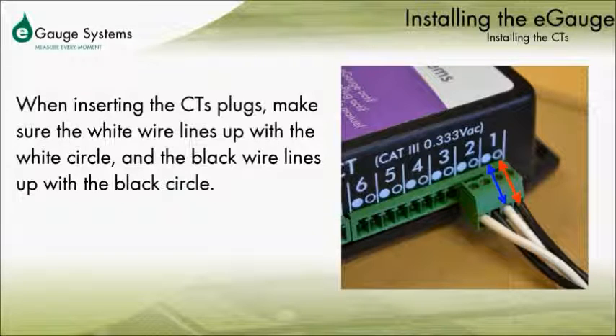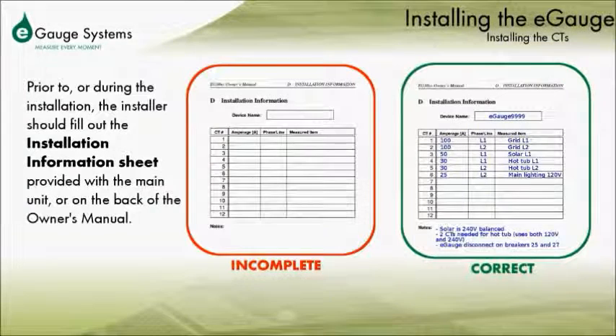When inserting the CT into one of these slots, please be sure the white wire lines up with the white dot and the black wire with the black dot. You can see this below in the picture. As the CTs are being installed, the installer should fill out the installation information sheet, which is located on the back of the owner's manual.